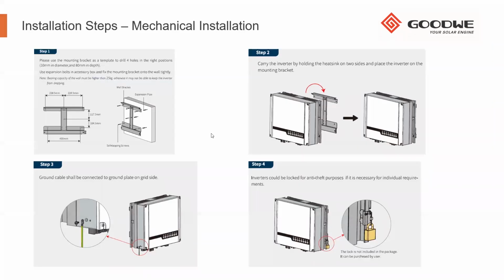For the mechanical installation, we do provide an easy to use wall bracket and the bolts, but depending on your wall structure, you might provide your own bolts to mount this. We provide the dimensions for the unit and the spacing to leave, so you can measure this out on the wall, or you can just use the bracket against the wall to measure. The inverter simply hooks up on the bracket, and then you can secure it with a securing lock if required. You'll see the ground cables should be connected to the outside of the inverter.